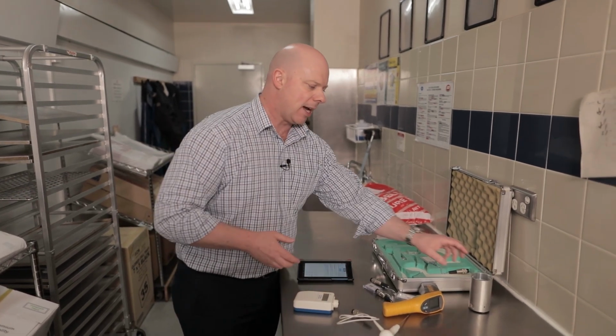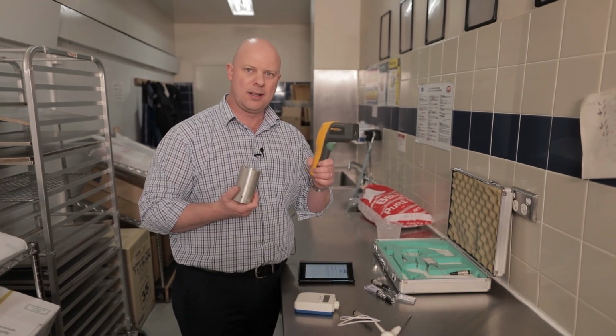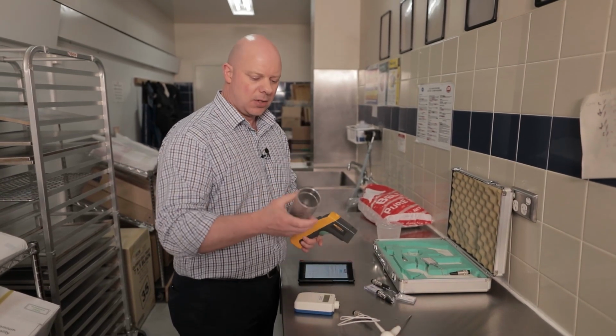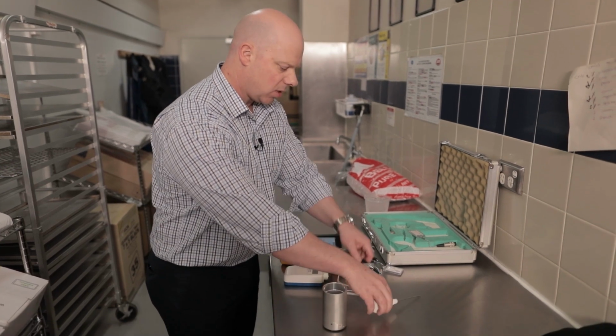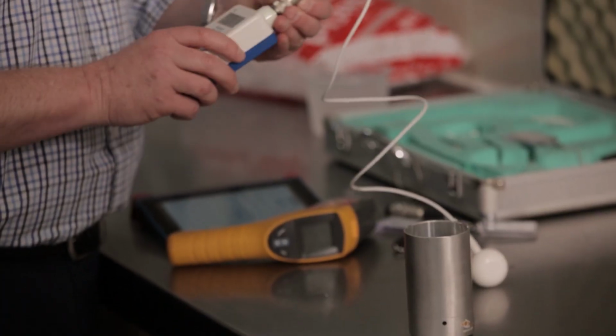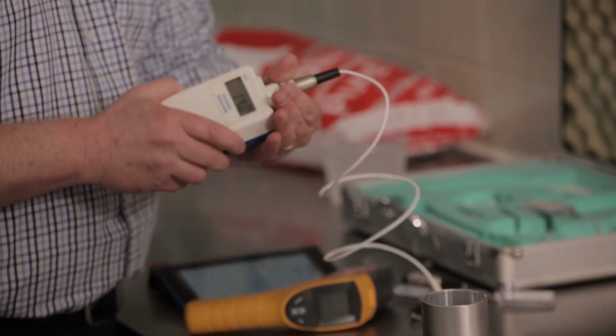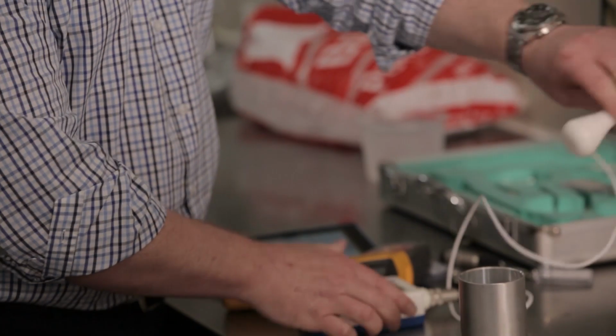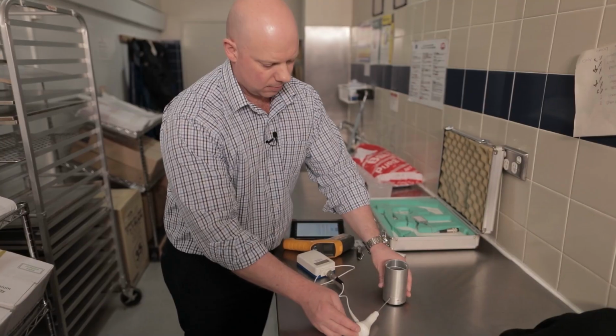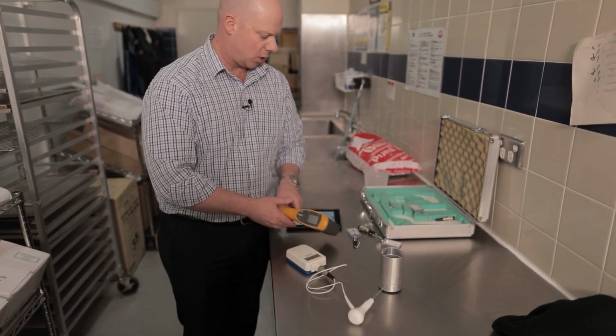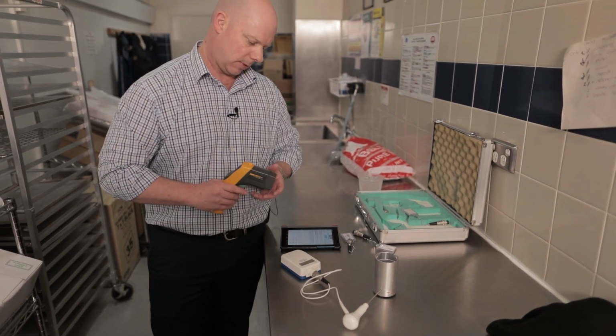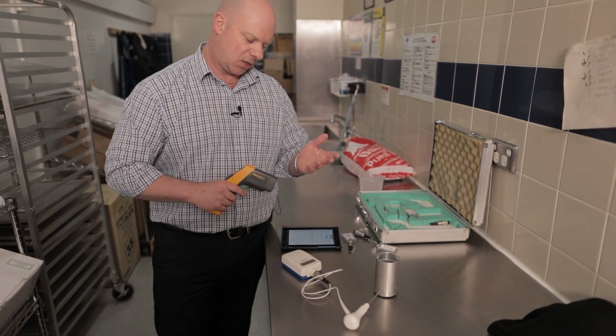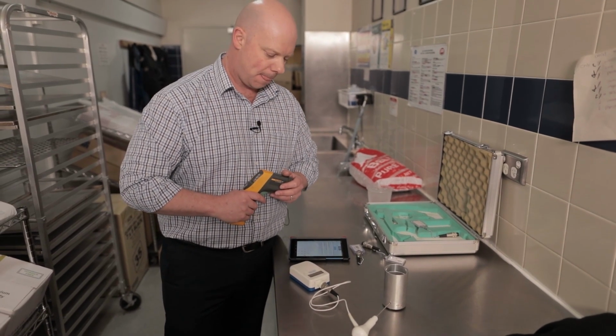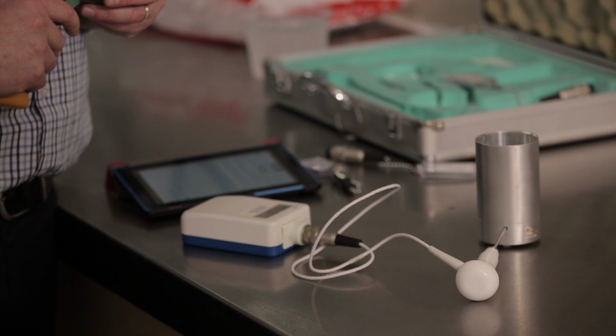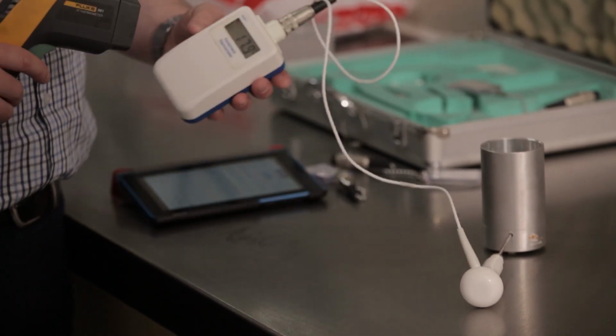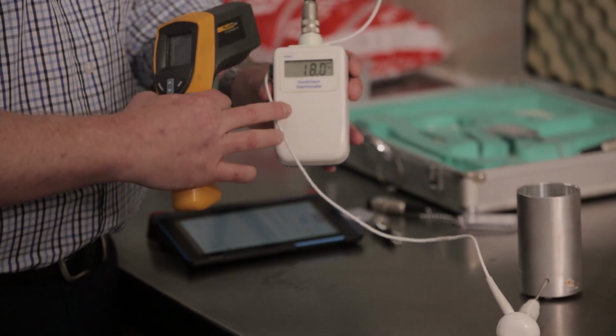Because we know they're accurate, we're now going to use this comparator pot to test our IR, our infrared gun, against our digital thermometer. So with the little holes there, just going to plug back in my probe. And I'm going to stick my probe into the little hole there. I'm going to wait for the temperature to regulate. It's sitting at 17.5, which is where we had it before. 17.7. 18 degrees.